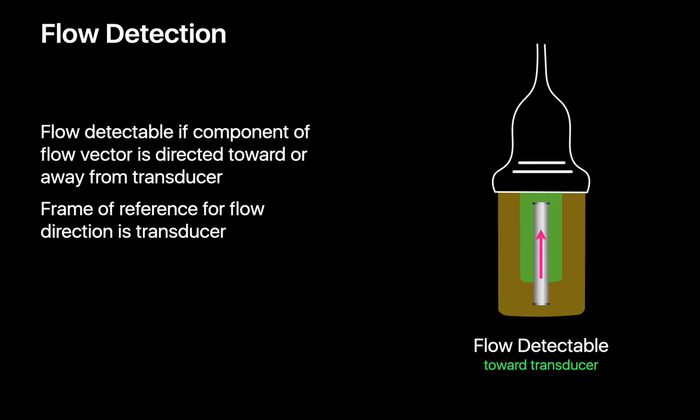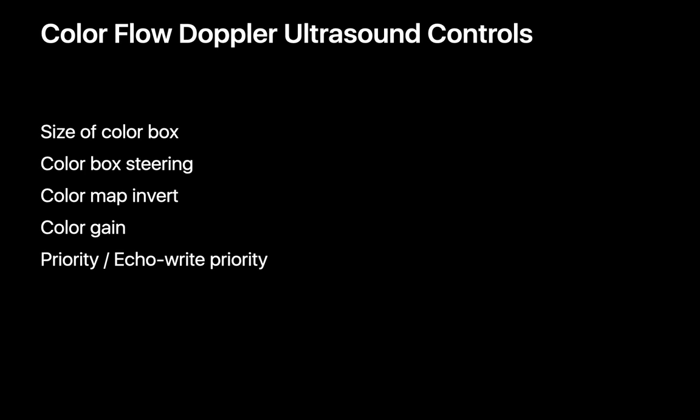Color flow Doppler imaging is able to distinguish and visually render whether the axis of flow relative to the transducer head is approaching or receding. When doing color flow Doppler imaging, there are five parameters you need to control: the size of the color box, steering the color box, which color — usually red versus blue — you want to assign to flow heading towards versus away from the transducer, color gain, and echo-write priority.